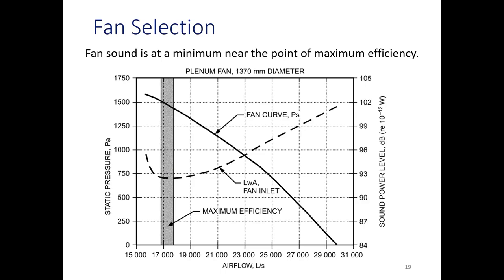So one of the things about noise vibration control, there's lots of ways to attenuate the noise, but sometimes you don't have a lot of space. And fitting in a silencer might be about your only option. And you might need to get a lot of attenuation out of that silencer in a short distance. And when you do that, it adds a lot of pressure drop. Like, some of these systems might only have an inch and a half of pressure drop, but you want to come in and add a silencer in there that's like a quarter of an inch or more. So you're adding one-sixth of the pressure drop you want to add to it.